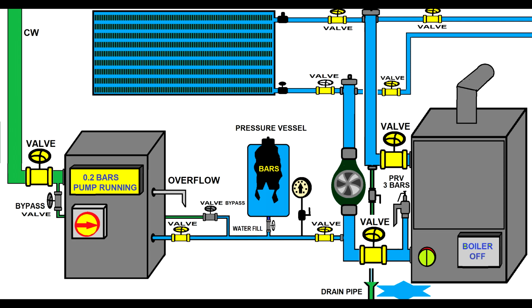So you have to be really careful how you design the system. We really have to pay a lot of attention to this elasticity. We have to pressurize the pressure vessel with the right amount of pressure, and also we have to choose the appropriate pressure vessel. We have to make sure that the pressure vessel can allow the heating agent to expand, and in this way we will avoid an increase in pressure in the system. So by choosing the right pressure vessel, we can keep the pressure variation of the system under control.